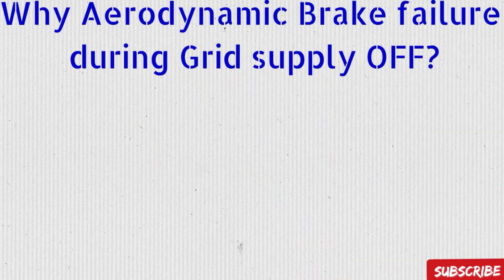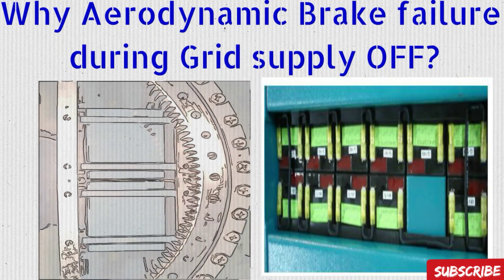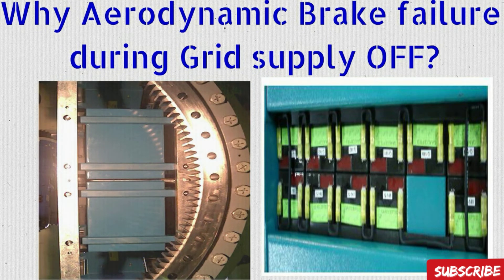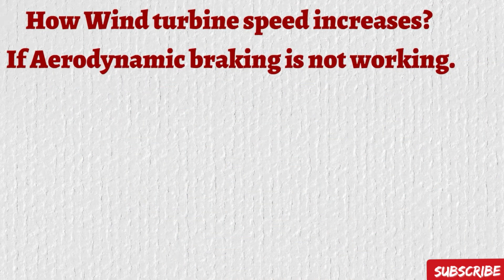Why does aerodynamic braking fail during grid supply cutoff? Generally during grid cutoff there is no supply in the wind turbine, but we immediately need to rotate the rotor blades from 0 to 90 degrees — otherwise rotor speed increases. For this purpose a battery bank is used for each blade. If the battery bank fails, aerodynamic braking will not work, because the battery bank is what provides backup power to the pitch motor through the VFD controller. So battery bank maintenance is very important in wind turbines.